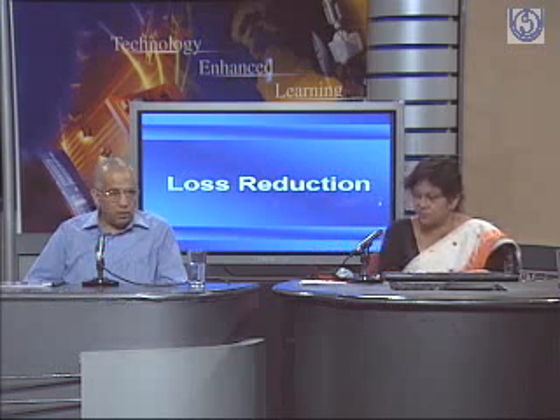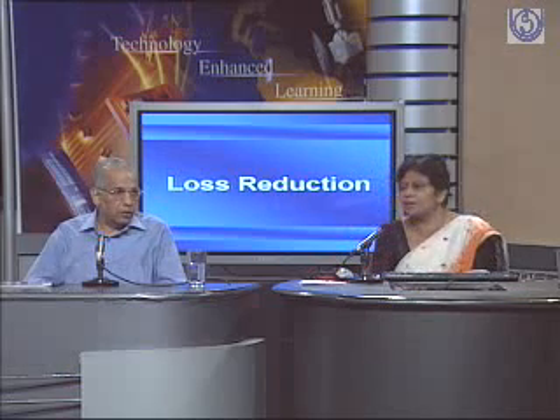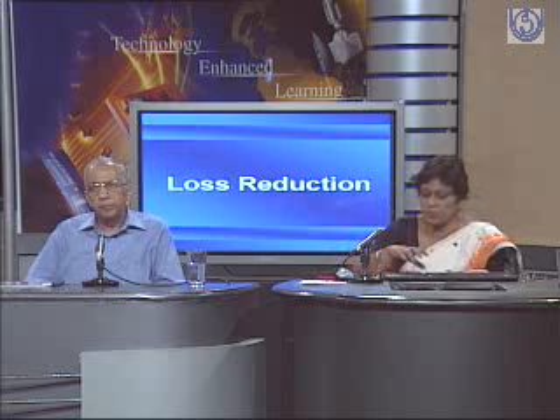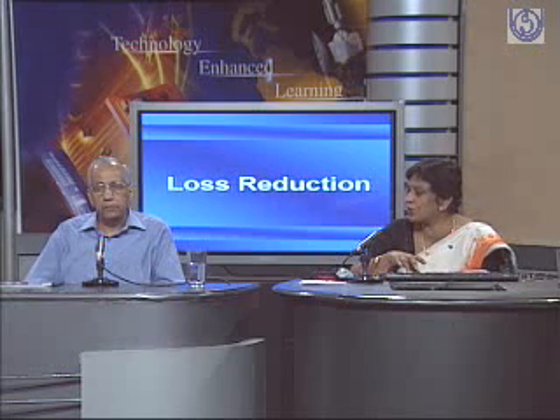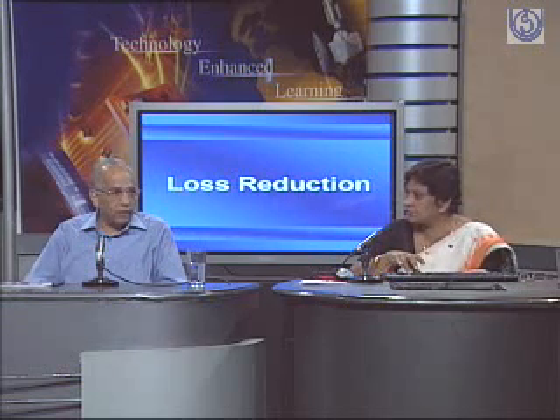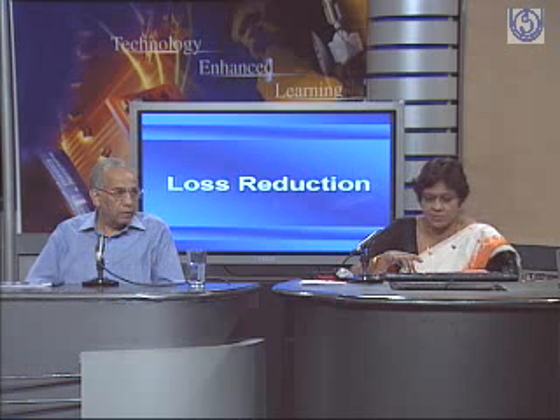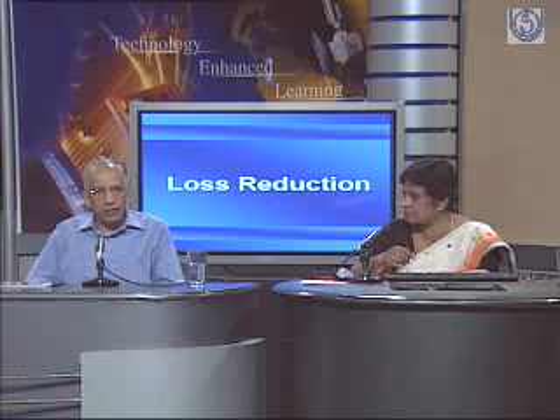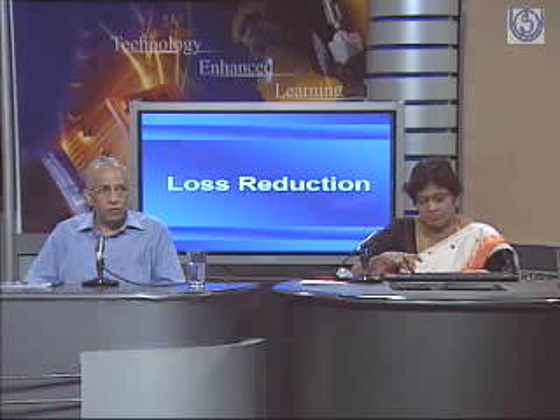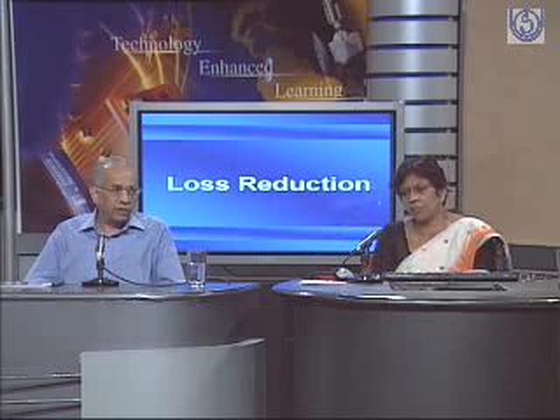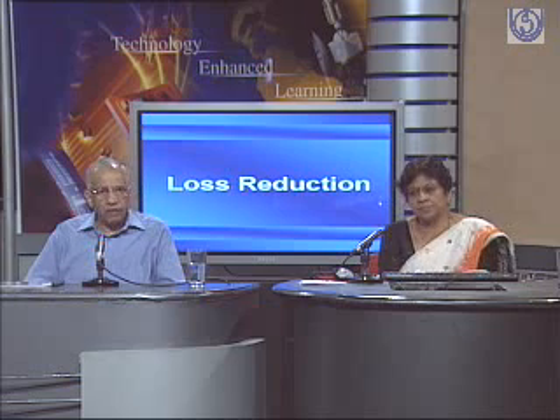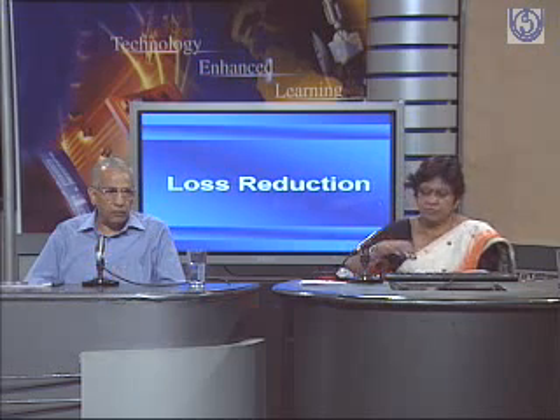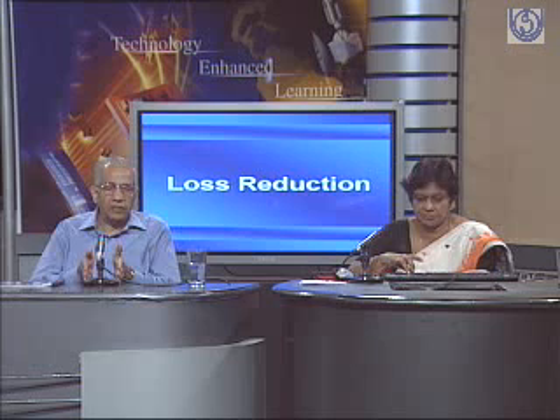So you have to provide the proper capacity transformer, and the load sanction has to be there. They must not exceed the sanctioned load. You should not be putting more load than the sanctioned load, and when you steal, you try to put more. So they must apply for a fresh increase of the load. Yes, that is true. In that case, you will have to change the transformer. Of course, a better practice in my opinion would be that you take a margin in the transformer capacity and check the theft of electricity by some other means. Otherwise, if they take a lesser connection, you provide a lesser transformer, and then you change the transformer.